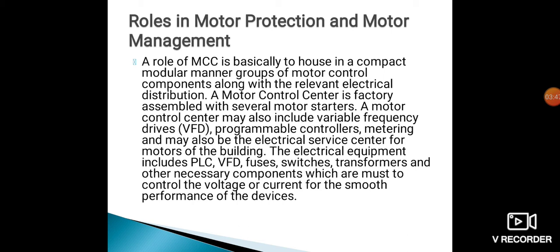A Motor Control Centre is a factory-assembled device with several motor starters, as MCC controls N number of motors. An MCC may also include a Variable Frequency Drive to control the speed of the motor (VFD), programmable controllers for automatic control, and meterings to take different readings. It may also serve as the electrical service centre for motors of a building.